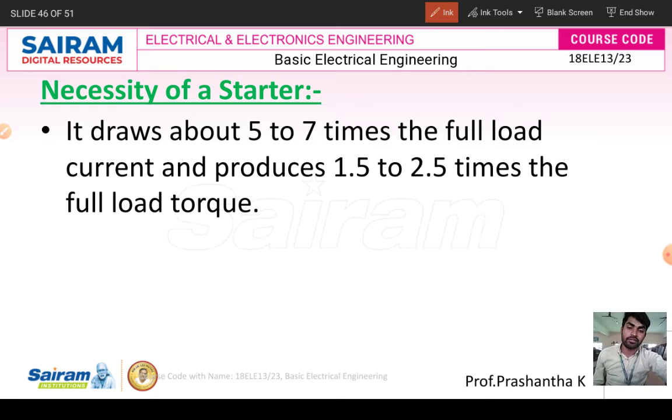Like 5 to 7 times, because there is no back EMF, there is no rotation in the rotor. Once the rotor starts rotating, it creates EMF, and the rotor then rotates smoothly. So it is 5 to 7 times. Also the torque required at the time of starting is 1.5 to 2.5 times the full load torque, right?